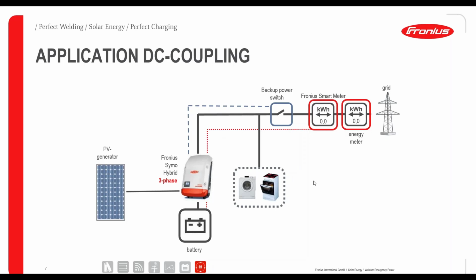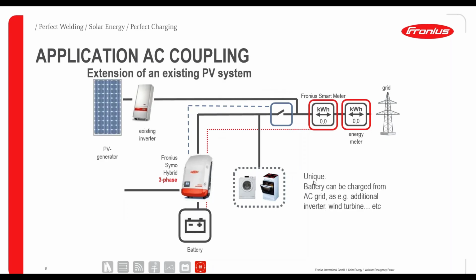When you have an existing system, you can also use the application AC coupled. Here you see there's an existing inverter with a PV generator, and you add the AC coupled system of a battery. In this case, the power flow will go through the second inverter. Basically, from this existing inverter it goes to AC, and then via the Symo Hybrid to DC again, and then to the battery. So this would also be a possibility, a typical AC coupled battery system. With our system, we also have the advantage that we can add a PV generator on the Symo Hybrid as well. With that, you have the possibility to recharge the battery even in a blackout situation.